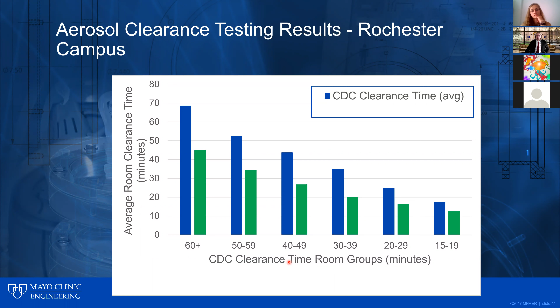And as we went through, we had pretty good results all across the board. You can see the blue line was the standard clearance time based on CDC guidance, and the green is on average our measured air clearance time. And this is probably a little better chart for looking at it. This is a group of operating rooms, and you can see across this group there was on average a 40% reduction in the amount of time we had to leave a room empty.